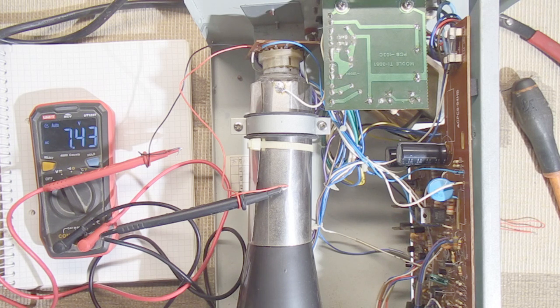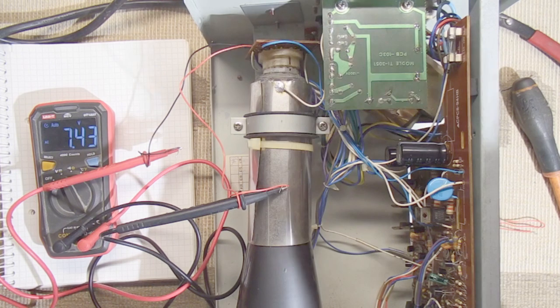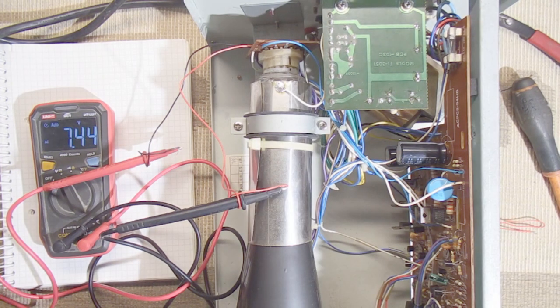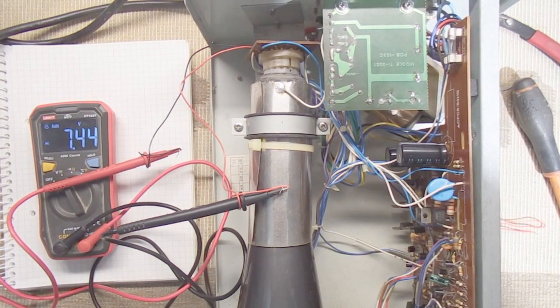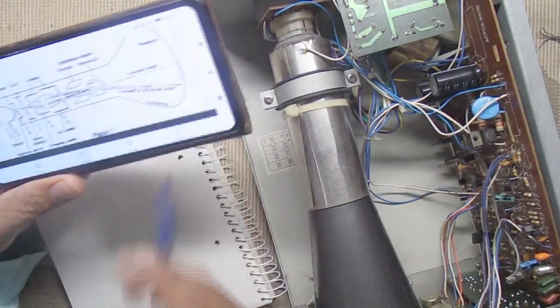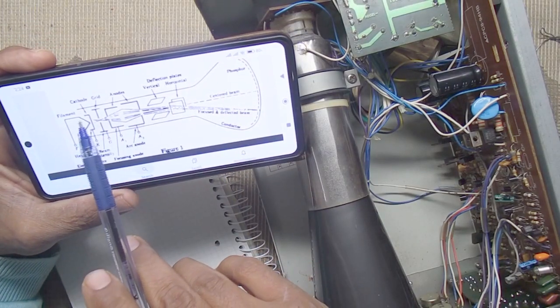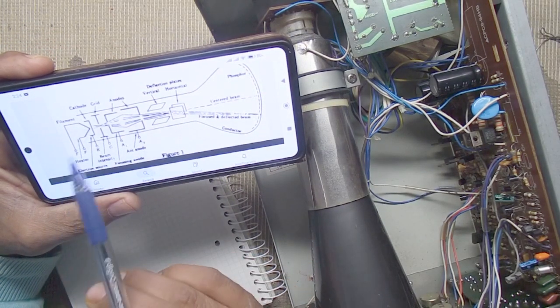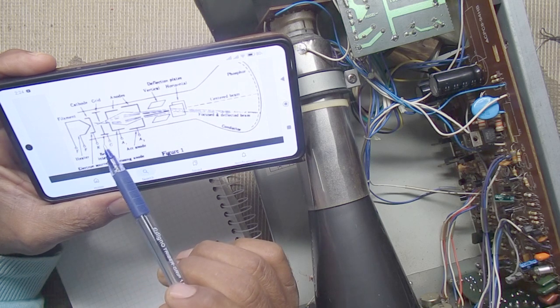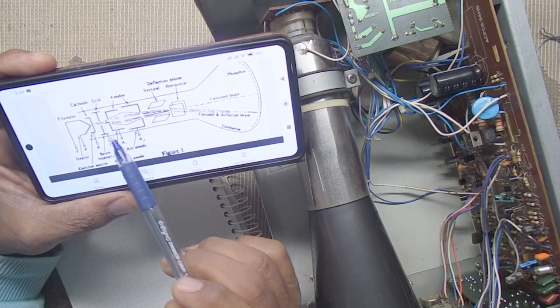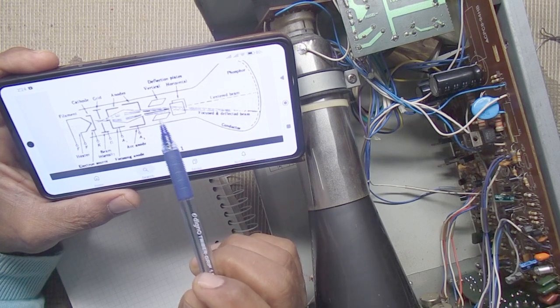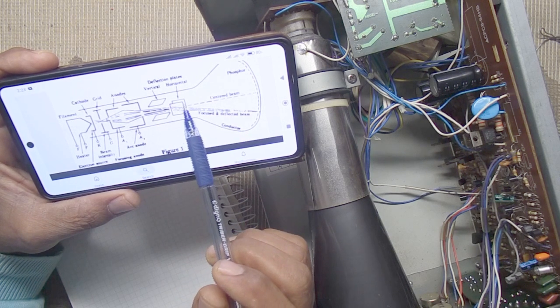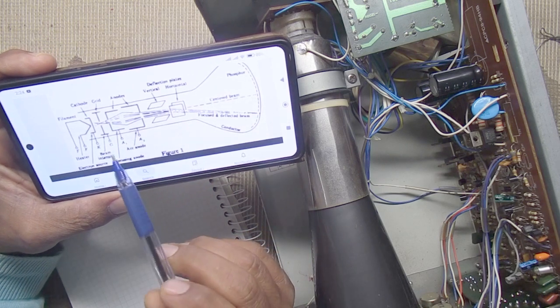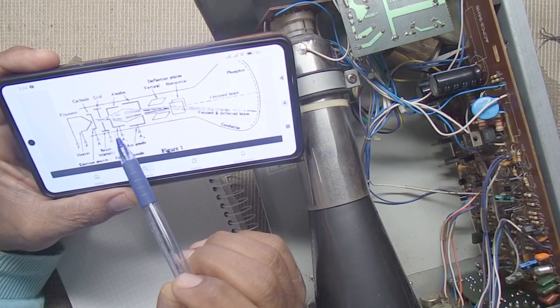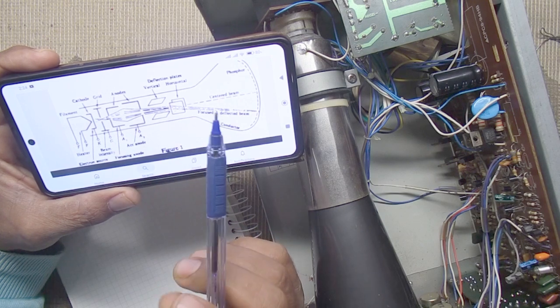I will remove these leads and we will see if our voltages are okay or not. Here we have a schematic of the CRT tube. We have here the filament, here the cathode, the grid, and the anode. And here we have the deflection plates, the Y plate and the X plate. So what we need here is the accelerating voltage, because we have no electron beam.